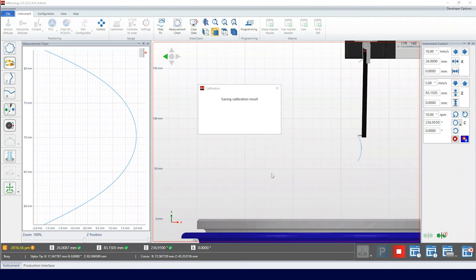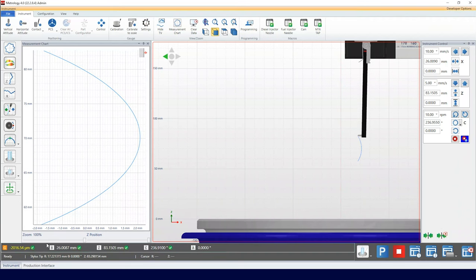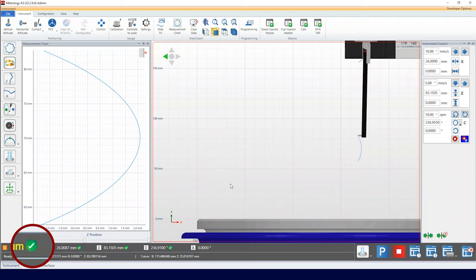Once the calibration is complete, the green tick indicates the calibration has been completed and is valid for 8 hours.